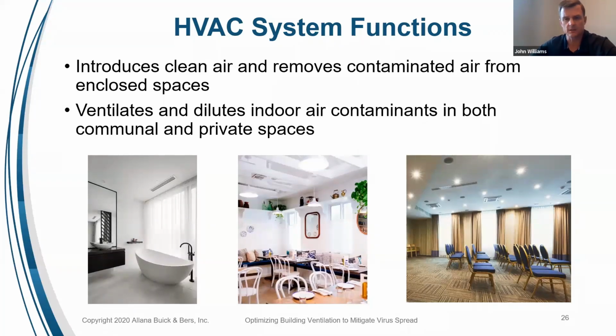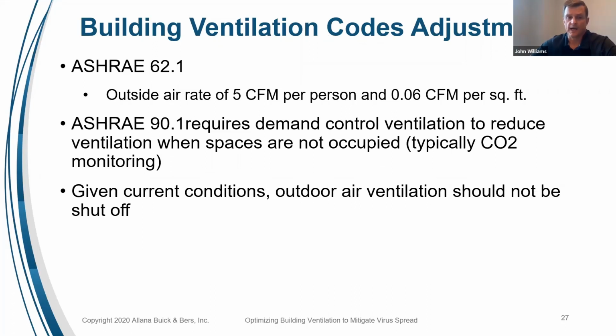In public buildings especially, these systems are designed to bring in clean, fresh air and to remove contaminated air from our buildings. We had touched previously on some ASHRAE items. I'm not trying to kill people with numbers, but ASHRAE 62.1 says that we need to have an outside air rate of 5 CFM per person and 0.06 CFM per square foot. And when we're using demand control ventilation, which is another ASHRAE requirement for new projects now, typically CO2 monitoring, we actually want to disable it with the current conditions.